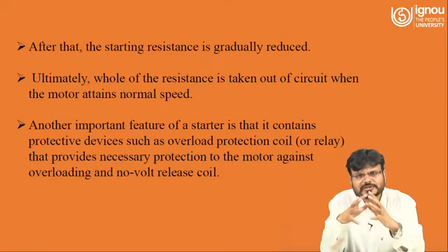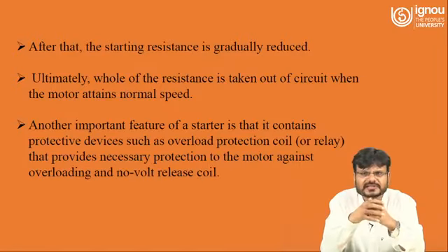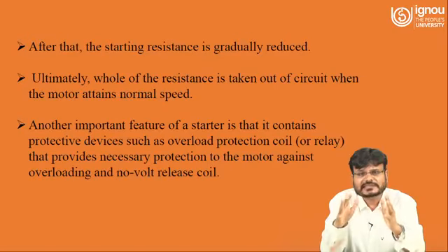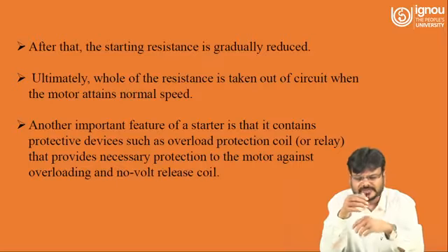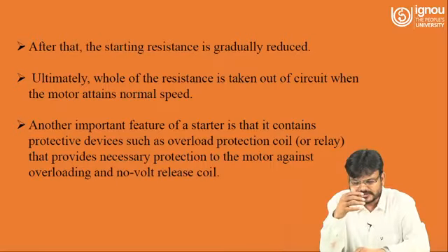Another important feature of a starter is that it contains protective devices such as an overload protection coil, or you can say a relay, that provides necessary protection to the motor against overloading, and a no-volt release coil. So by any means you have to put some extra resistance in series with the armature.